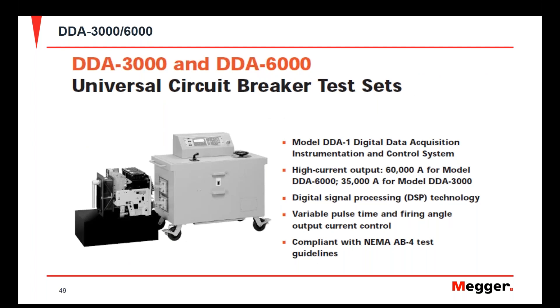Another instrument for primary injection testing is the DDA, which comes in two versions: the DDA 3000 and the DDA 6000. The DDA 3000 provides as much as 35,000 amps of test current, and the DDA 6000 provides as much as 60,000 amps of high current output. Both units are operated by the DDA 1, a digital interface for breaker testing. The unit offers variable pulse time and firing angle to negate the influence of challenges encountered during primary injection testing. This test set is also compliant with NEMA AB4 for breaker testing guidelines.